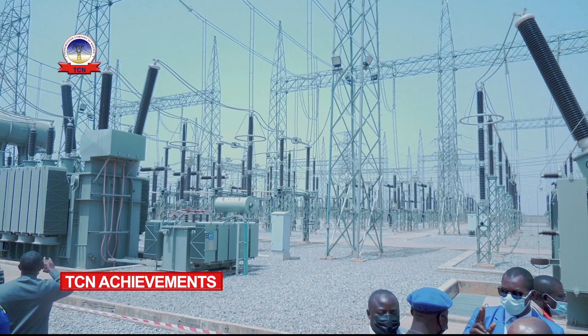As at the time of inception, that is in 1976, we had only 5 MVA transformer, and we had one outgoing 33 kV feeder feeding Birnin Kebbi Township with a load of less than 1 megawatt then. Consumption was not much. We had Niamey 132 kV line and Sokoto 132 kV line that were commissioned in subsequent years, around 1984-1985. Presently, we have a 150 MVA transformer, plus the first and second 90 MVA transformer. The capacity of the station is now 2 by 90 MVA and 150 MVA.